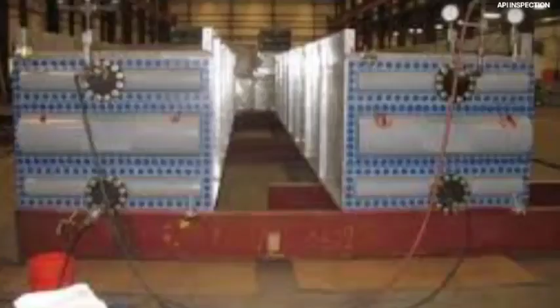So are you supplying this item loose? No, sir. It's a complete assembly, combined with the vessel. It's not a single unit. We'll have piping spools as well as this cooler. For the cooler, we make it as a separate assembly, so for that entire assembly we need to give a CRN number. These are the fittings we have used, and we need to submit those documents for the supplier in Canada. If the equipment is supplied to Canada, we need to provide the CRN certification for the equipment.